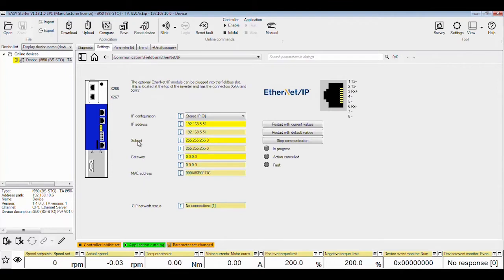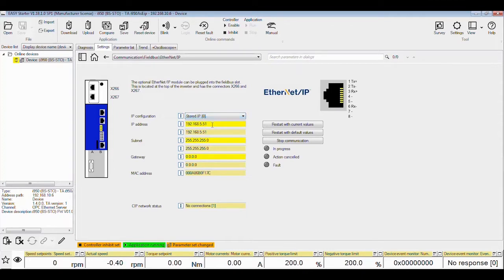By default, the IP configuration of the drive will be DHCP. You can change it so that the i950 will have a fixed IP address by selecting Stored IP instead. You can then change the IP address, the subnet, and the gateway to your appropriate values. Then click on Restart with Current Values, and you should see the active values change in the read-only yellow boxes when it's done.